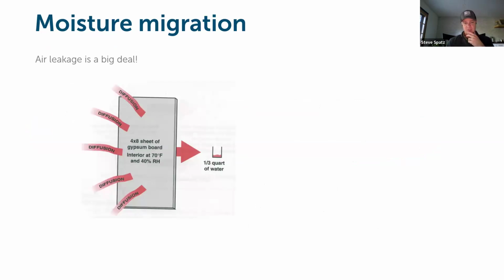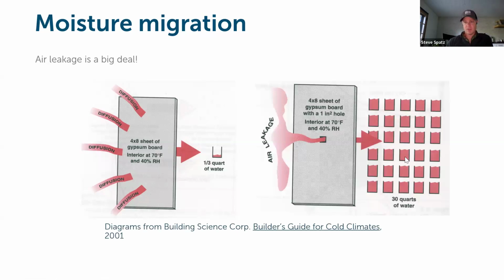So just as a kind of a physical example of this is a pretty well-known study that was done by the Building Science Corporation many years ago, of looking at vapor diffusion through drywall into your average insulated building assembly. So through a typical heating season, a 4x8 sheet of half-inch drywall that's seeing an average temperature of 70 degrees and an average relative humidity inside the building of 40% throughout the heating season, you'll get about a third quart of water diffusing through that material during that heating season. But consequently, if you put a 1 square inch hole into that same 4x8 sheet of drywall, that has the potential then to transport up to 30 quarts of water into the assembly behind it.